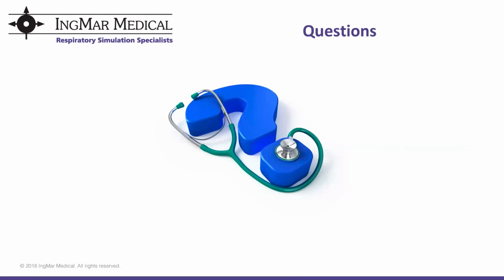The easiest way to answer it is that the amount of space available in an ASL's piston does not allow enough time for a flow to evaluate to give us an accurate result. However, we are working on a process by which we use an ASL in a flow pump or volume pump mode to deliver a constant flow to a secondary ASL, which would be the one under test. By this, we can get enough of a flow rate and we can automate that process whereby we could receive accurate linear resistance results. This is a work in progress and we hope to have something in the near future.